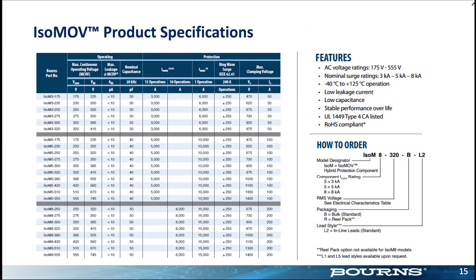All right. So if you look at the data sheets on an IsoMOV, you'll see the numbering system, the ISO-M3. The 3 stands for 3 kA or 5 kA or the 8 kA, multiple hit type of limit. You'll see the voltages there, up to 700 something volts. These are on the higher end of the voltage scale. And you'll see the one hit, 10 kA, 15 kA. These are pretty nice devices, actually. You won't find anything like this in the size in the market.